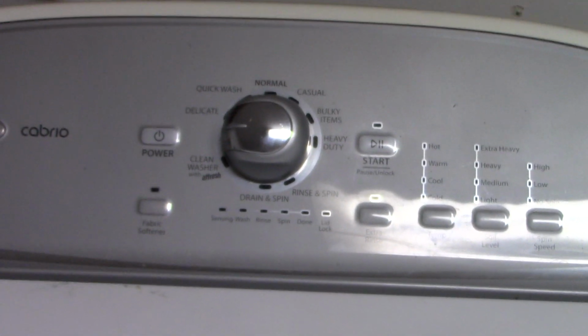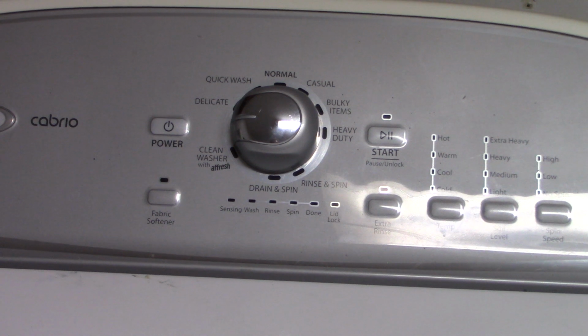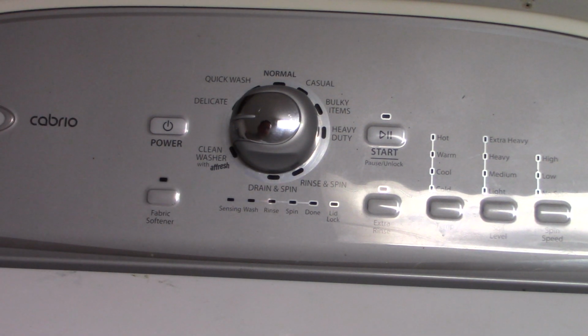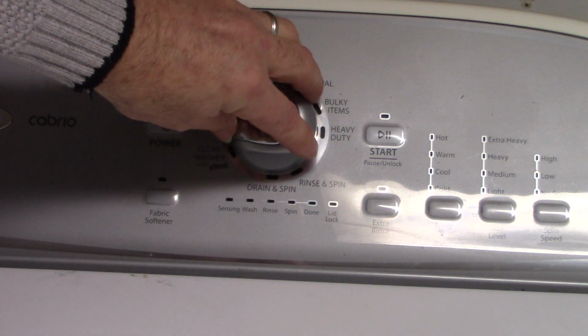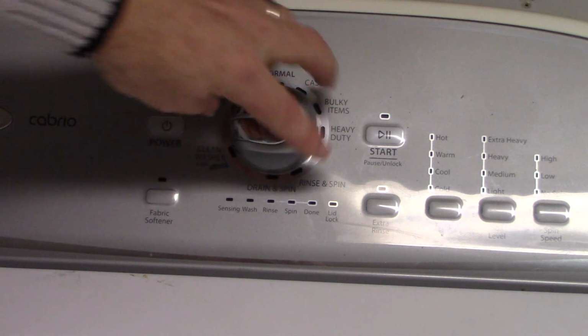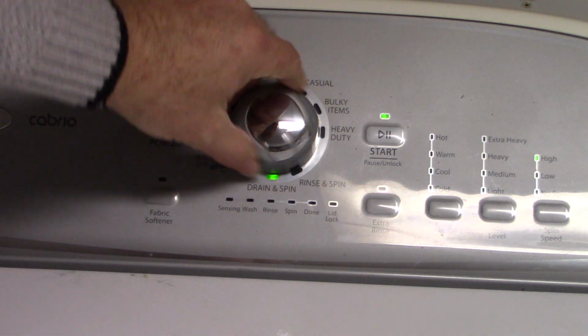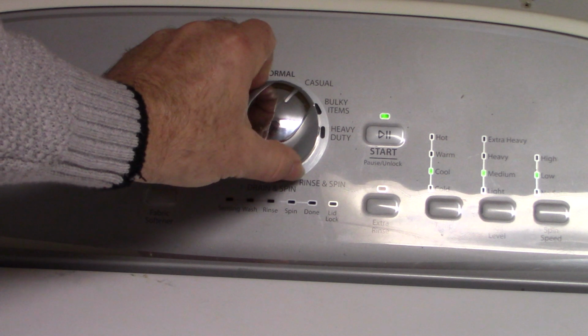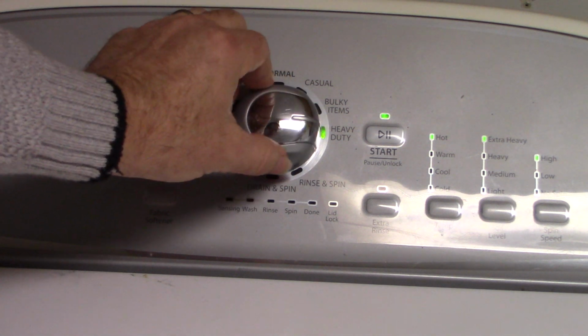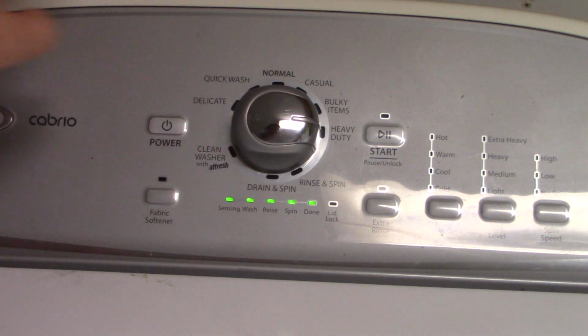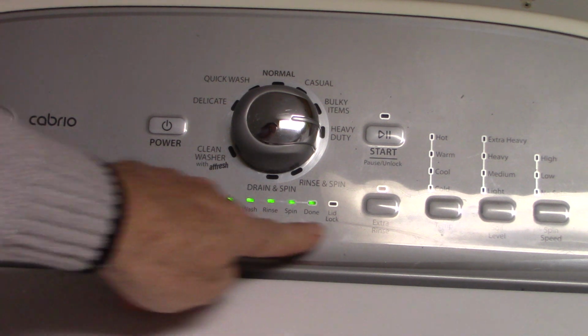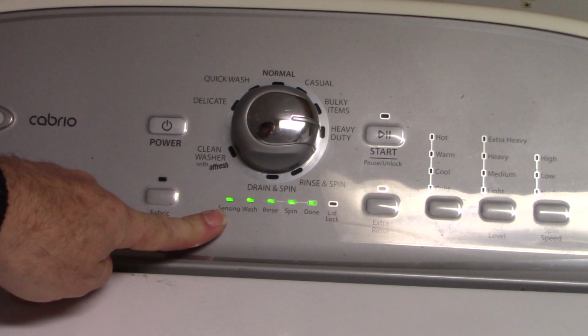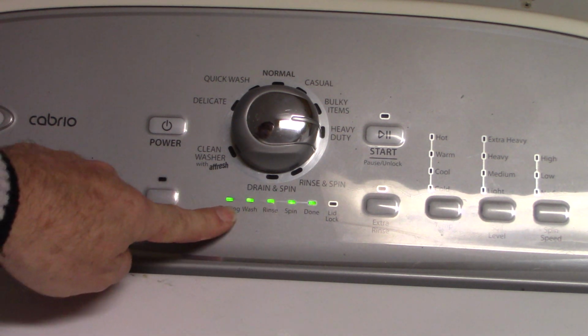Let me have you look at the dial, control, and the LEDs on the panel. Here's how we do manual test mode. You're going to take the dial and go a full revolution counterclockwise or more, then 1, 2, 3 clicks clockwise, 1 click counterclockwise, and 1 click clockwise. Now you've got diagnostic test mode. You'll know you're in it when all the lights are blinking.